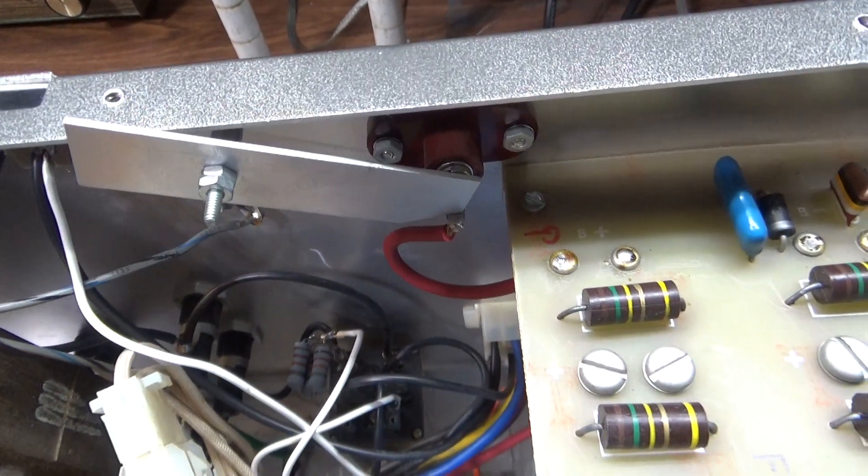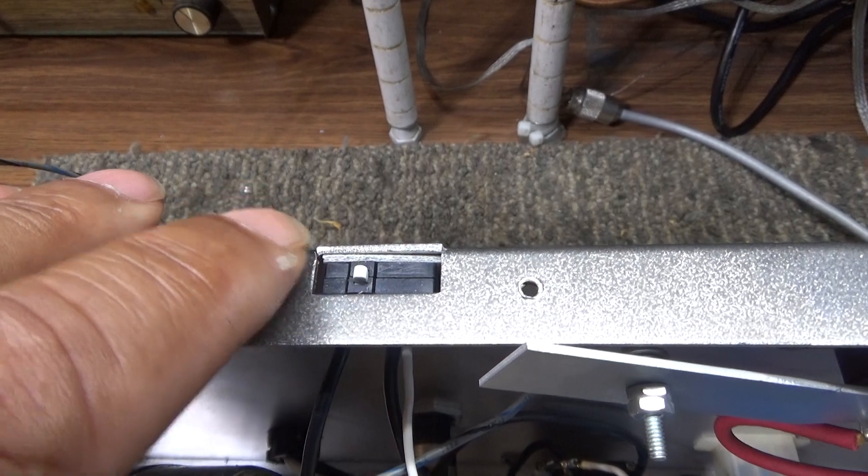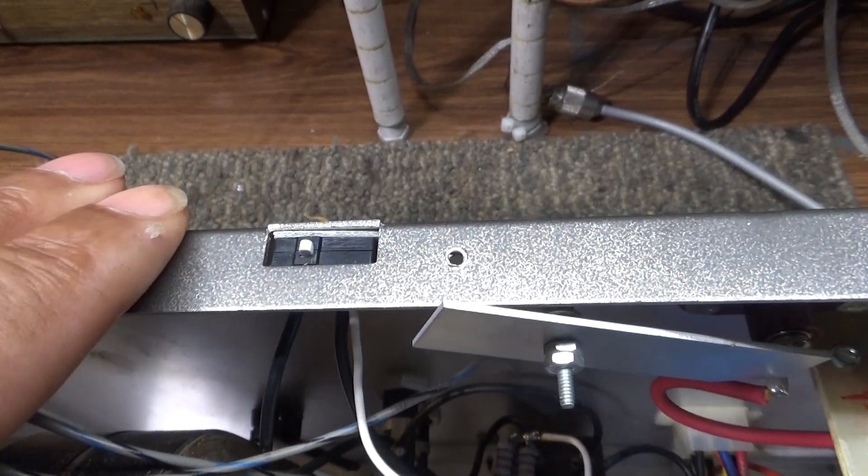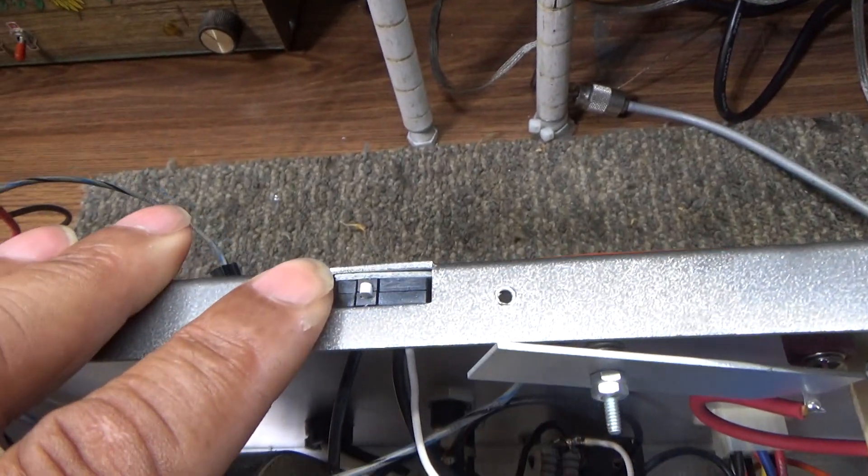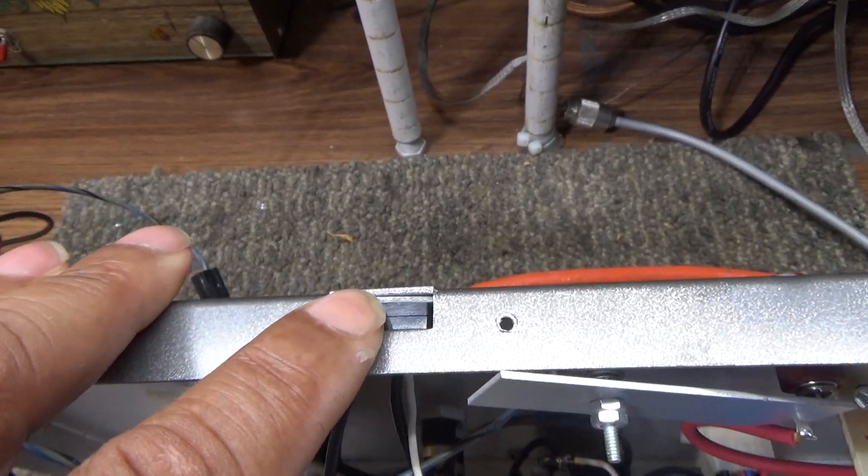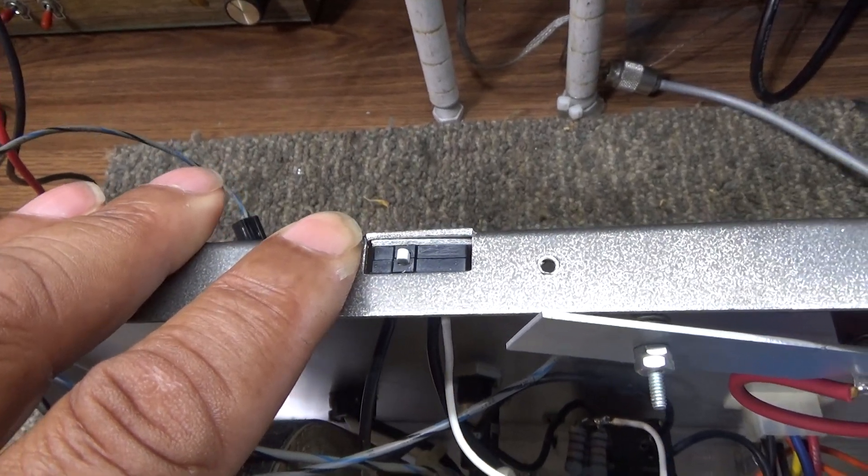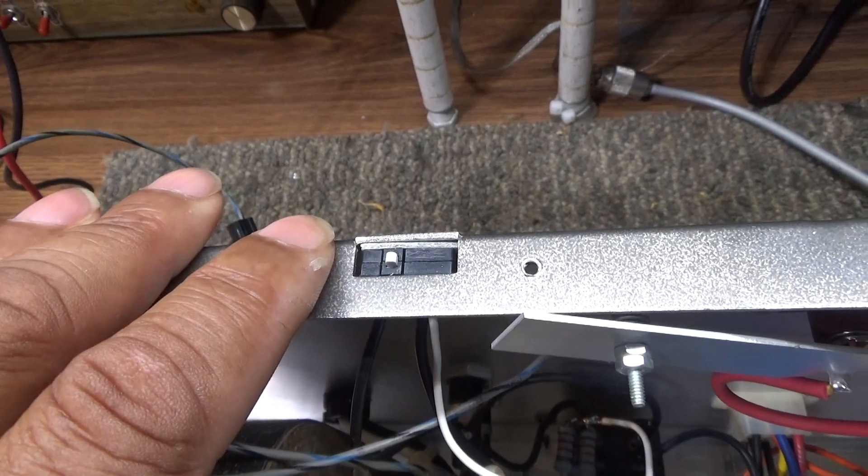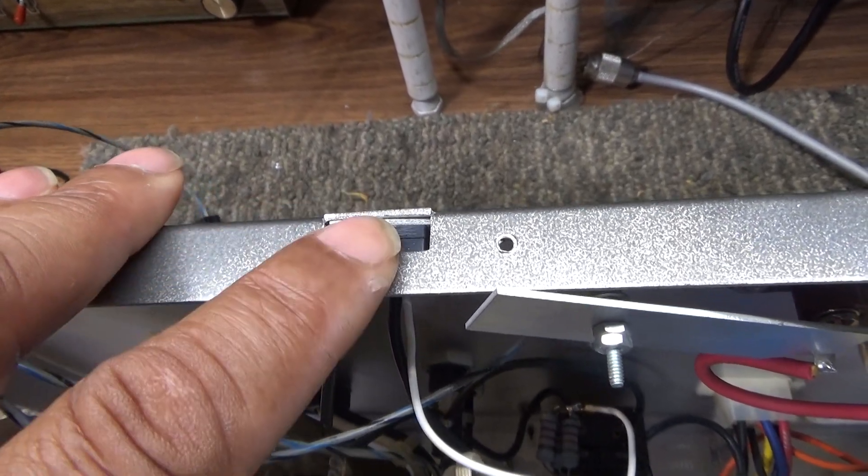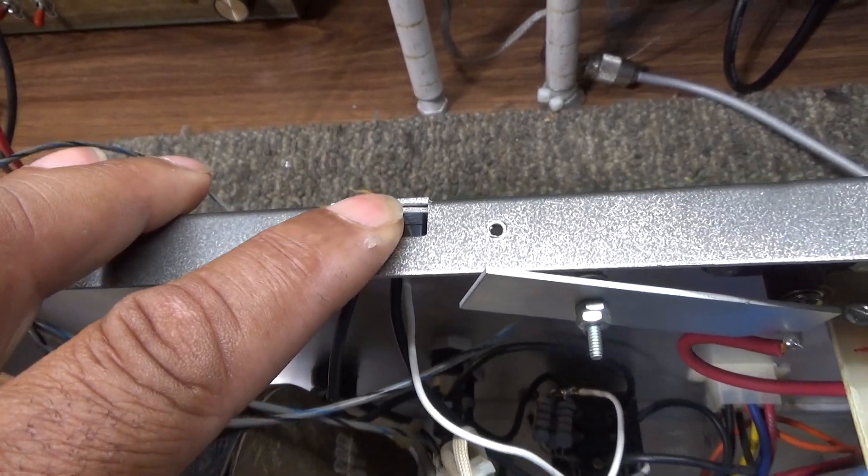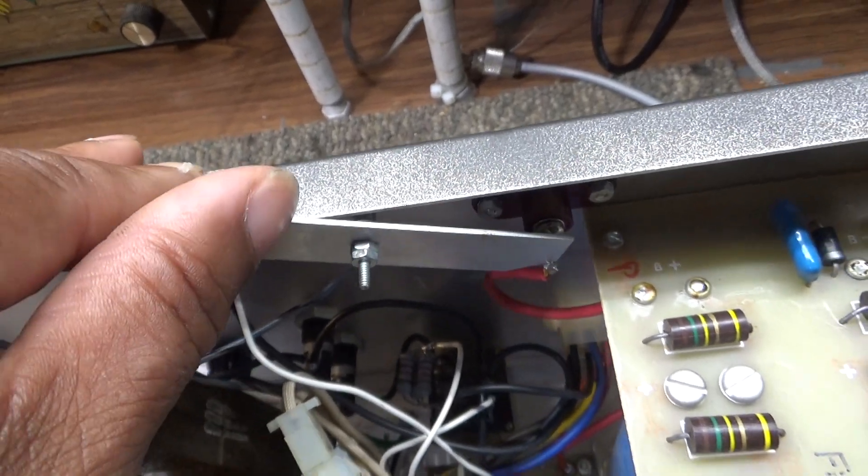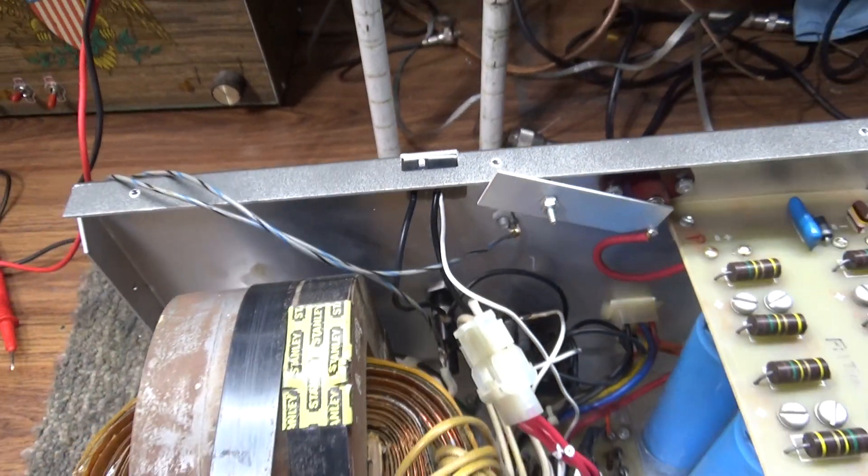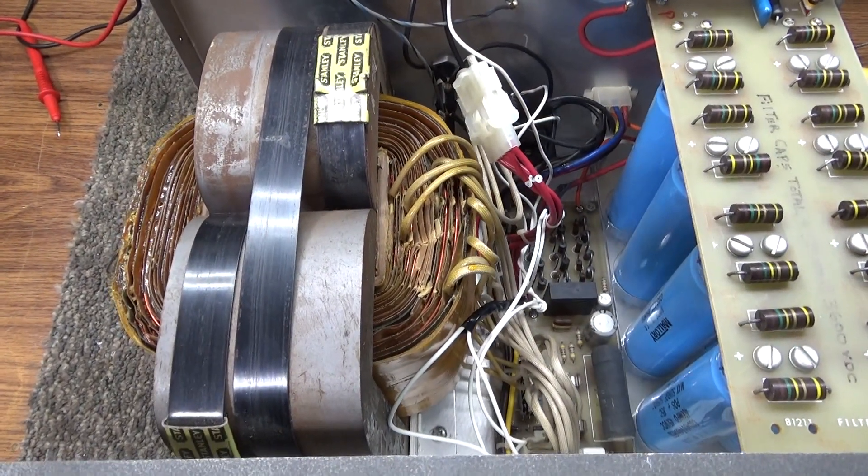There's also another safety switch, a little micro switch interlock. When you take the cover off, the power going to the relay to turn this thing on, this switch goes to the relay coil. So you can't power this up with the cover off because it opens this switch here. Those are your two safety features to try to keep people from killing themselves, because of course this thing is lethal.